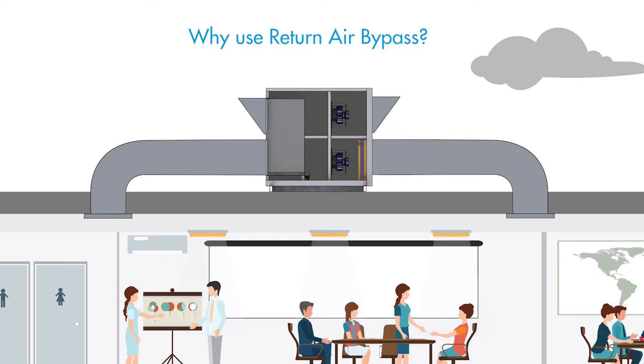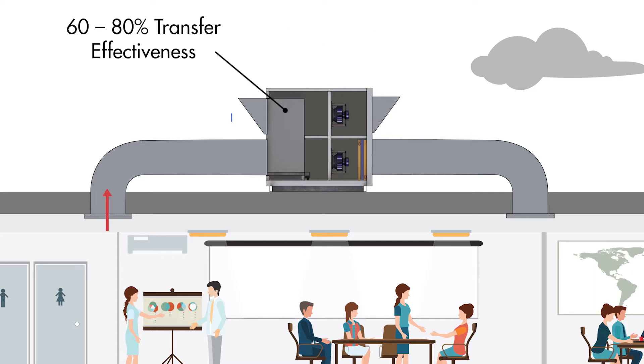To explain why Return Air Bypass mode is used, we need to point out that ERV and HRV units are not 100% effective. Typically they can transfer 60-80% of the heat or energy. So while they do a good job of minimising an outside air load, they are not as efficient as directly reducing or eliminating a fresh air volume itself, if a particular scenario allows it.